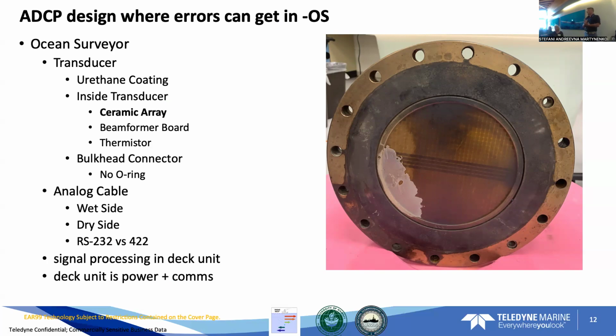And what we've been seeing with that failure is that it's not necessarily the RSSI, the intensity return, where you can really see the failure on the 2 beams. It's in the correlation data: these 2 beams that are both failing are very well correlated, and differently correlated compared to the good 2 beams. So it's more about checking the correlation data rather than the intensity or the return data.